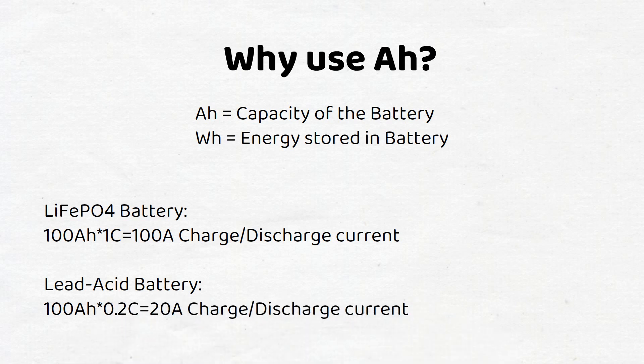Knowing this, we can calculate the maximum charge and discharge current for the battery under normal conditions. For example, a 100 amp hour lithium battery can provide a current of 100 amps, while a lead acid battery can only provide a current of 20 amps. A battery can provide more current, but that will decrease its lifespan because the cells will degrade faster.